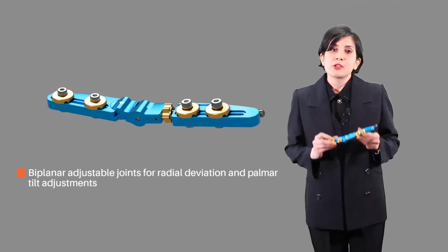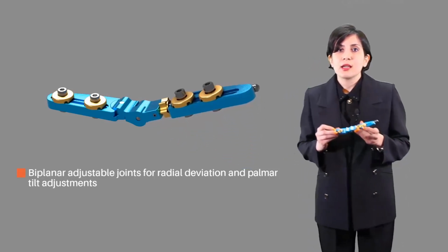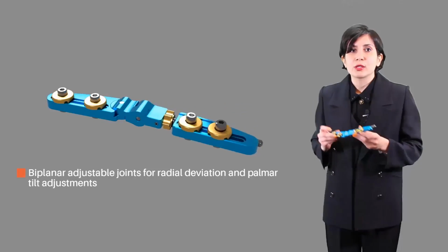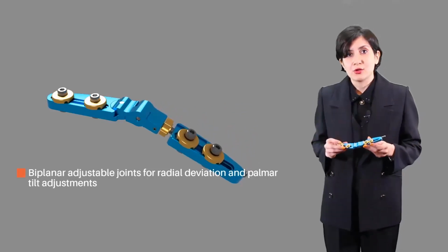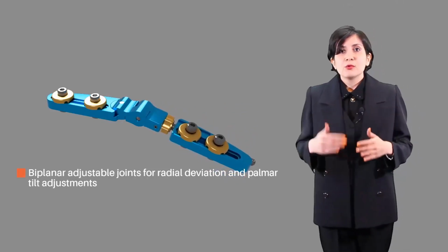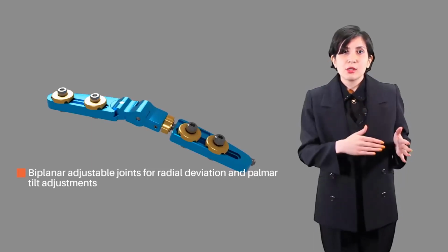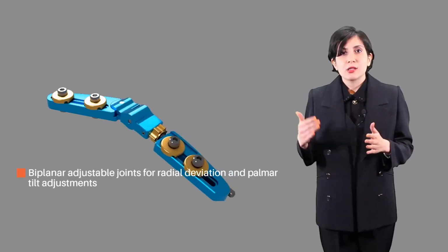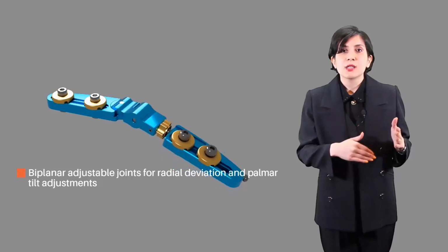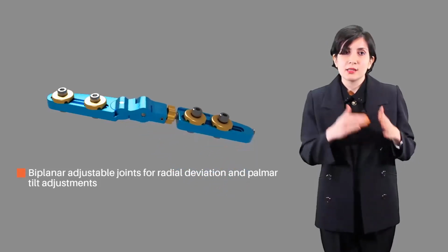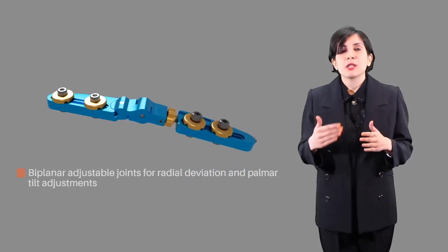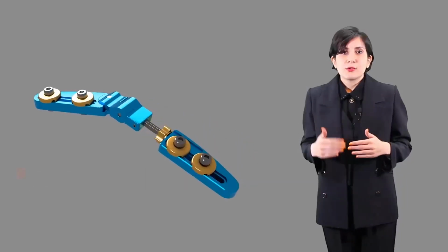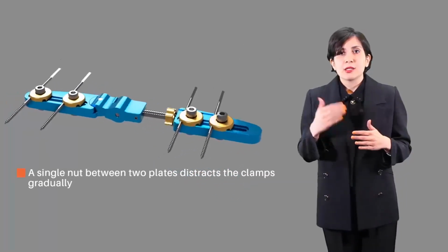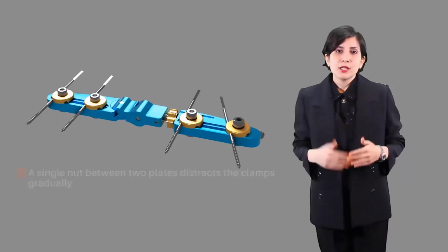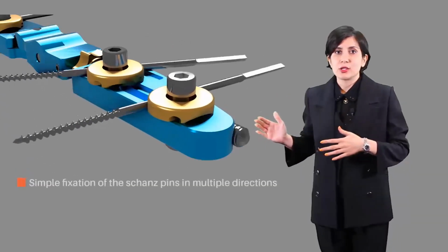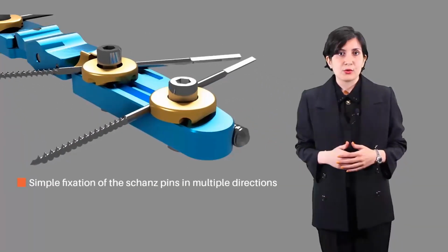The biplanar adjustable joints allow us to adjust the angulation in two directions according to the patient-specific fracture type and anatomy. The joint that moves in the vertical surface, the proximal joint, is equal to the intact side palmar tilt, and the joint that moves along the horizontal surface, the distal joint, will be equal to the radial inclination. The gradual distraction of the clamp is facilitated by a distraction nut between them. We can fix the Schanz pins in multiple directions, so simple with this external fixator.